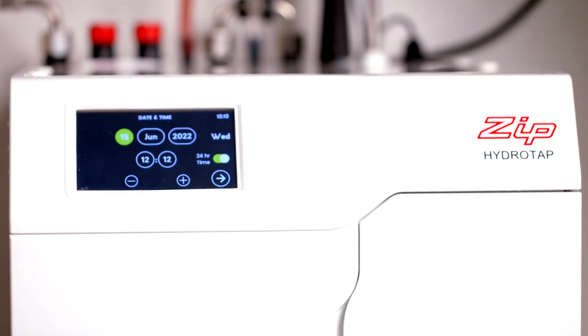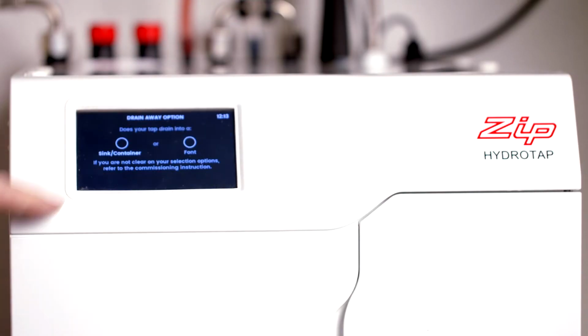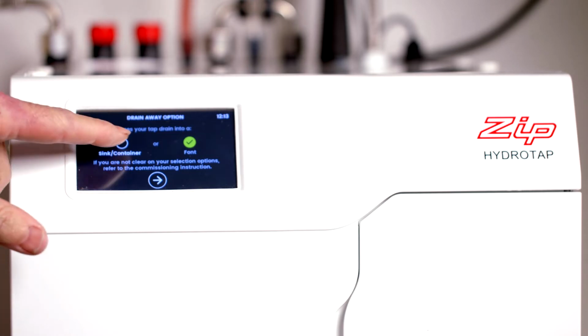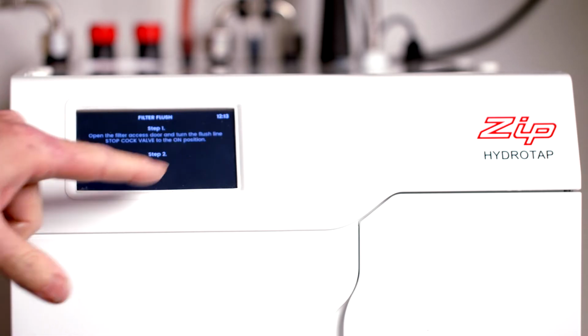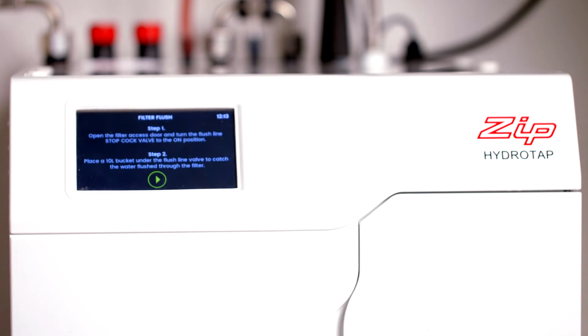This simply means if your tap or faucet is installed to dispense into a sink or the specially designed Zip font. If you select Sink Container, the flushing process from the tap will be automatic. If you select Font, you'll need to use the tap or faucet to dispense water during the commissioning process.